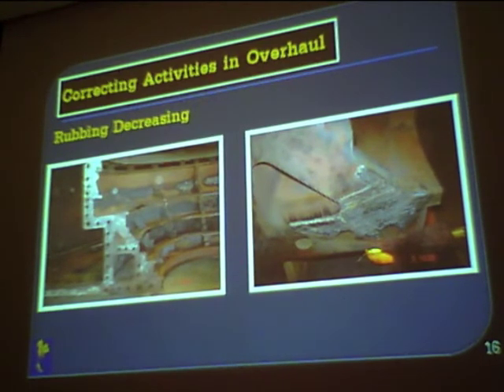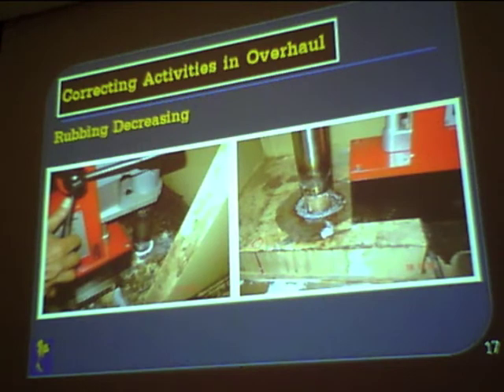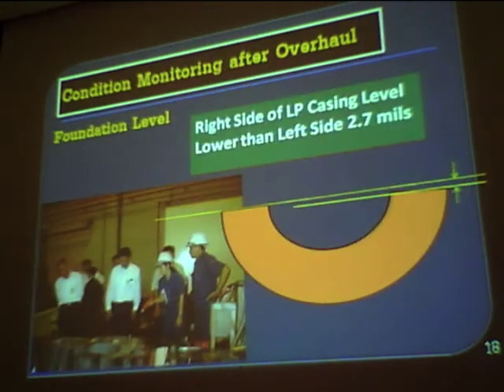We had to grind out the rubbing areas, weld them, and re-grind to make them smooth. We also addressed the anchor bolt holes in the LP outer casing, which needed to be enlarged to allow free thermal expansion during operation. Additionally, we found a foundation level issue — the right side was lower than the left by 2.7 mils. At that time we had no time to correct this, so we monitored it to confirm it remained constant rather than worsening.